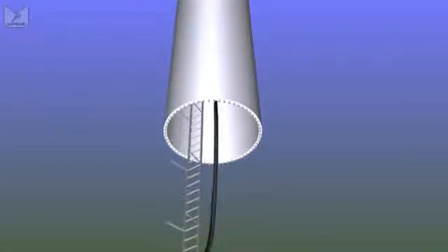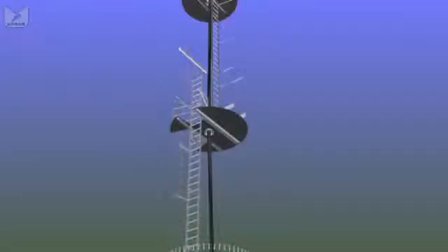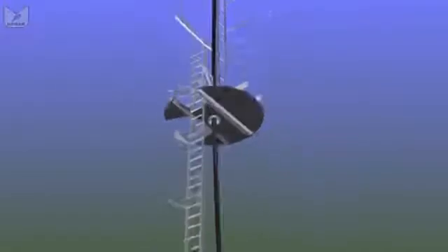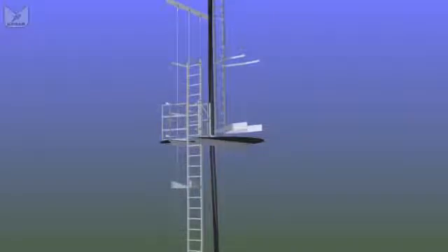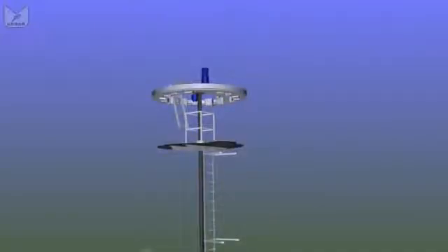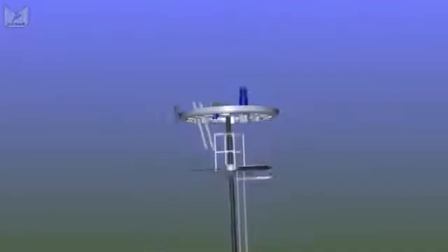The cable again breaks free from its mounting and hangs in the centre of the tower for the last 10-20 metres or so, so that it can rotate as the nacelle yaws into the wind, and the lift eventually runs out of space. Remember, the tower is getting narrower and narrower as we get to the top, so the lift tends to park itself about half a platform from the top, and we have a normal ladder which then leads to the yaw platform, and then it starts looking very much like the smaller turbine did.